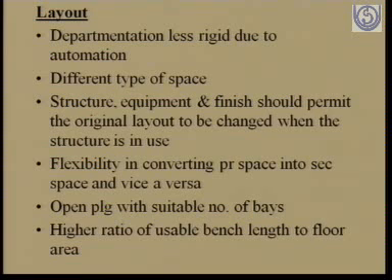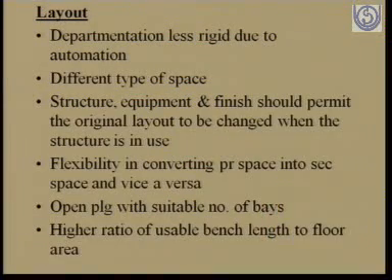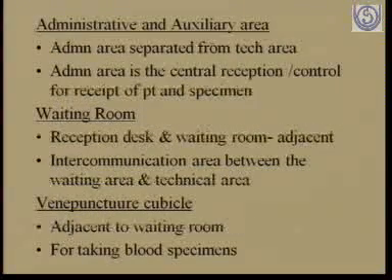Departmentation is now becoming much less rigid, except for the portion of mycology and microbiology. These sections need to be separate, but otherwise, due to equipment requirements, nowadays there is less rigid departmentation, and open space is preferred where you can install the equipment and work on it as far as laboratory staff is concerned. Flexibility in converting primary space into secondary space and vice versa should be available. Open planning, as I said, is a requirement nowadays.